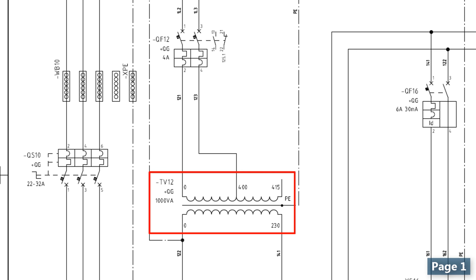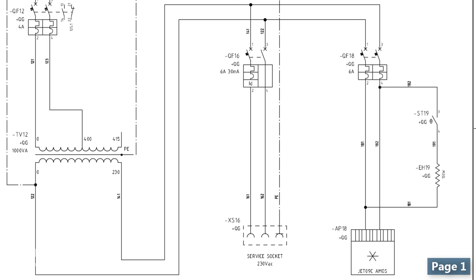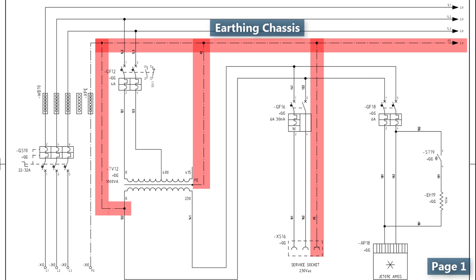There are the tags for the devices within the panel as well. If you were looking at the wiring diagram and you didn't know what this device is, then you could find it in the panel using this tag. This transformer converts the 400V to a single-phase 230V to fit the power receptacle or socket, the heater and the fan. The ST19 tag refers to a thermostat to turn on and off the heater or the fan on its specified temperature set points.